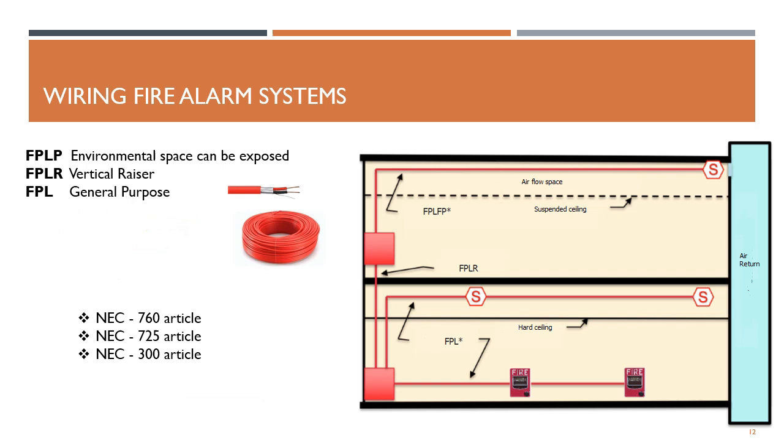FPLP, which is a cable with a stronger coating which allows it to be installed without using a pipeline. This can be pulled over the ceiling without pipeline without any problem. These are used when they are specified or when, due to the nature of the infrastructure, it is not possible to pull a pipe. Obviously, this cable is more expensive than the previous two.